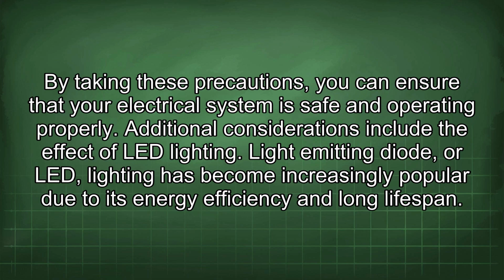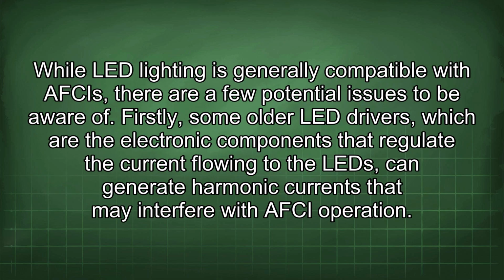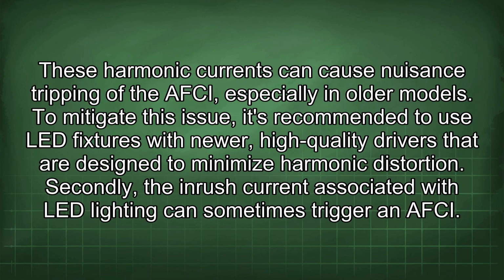Additional considerations include the effect of LED lighting. Light-emitting diode, or LED, lighting has become increasingly popular due to its energy efficiency and long lifespan. While LED lighting is generally compatible with AFCIs, there are a few potential issues to be aware of. Firstly, some older LED drivers, which are the electronic components that regulate the current flowing to the LED, can generate harmonic currents that may interfere with AFCI operation. These harmonic currents can cause nuisance tripping of the AFCI, especially in older models.